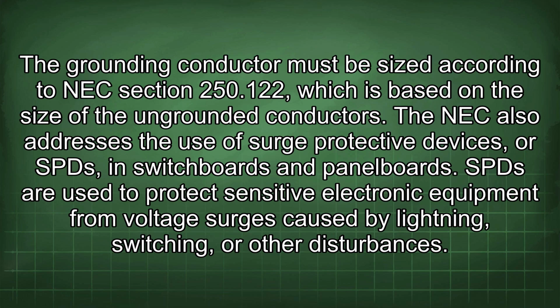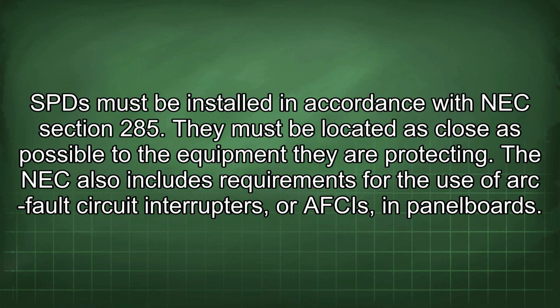The NEC also addresses the use of surge protective devices, or SPDs, in switchboards and panelboards. SPDs are used to protect sensitive electronic equipment from voltage surges caused by lightning, switching, or other disturbances. SPDs must be installed in accordance with NEC section 285. They must be located as close as possible to the equipment they are protecting.